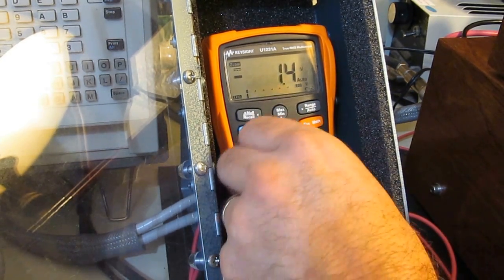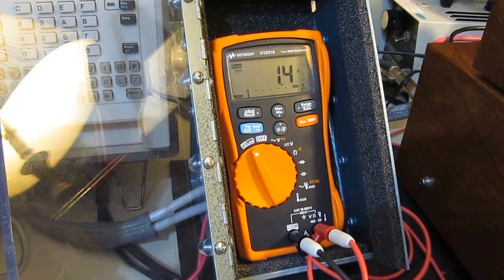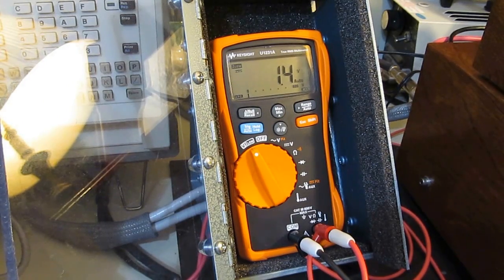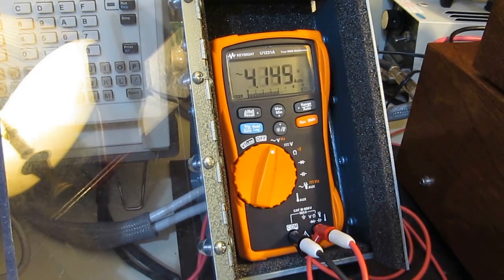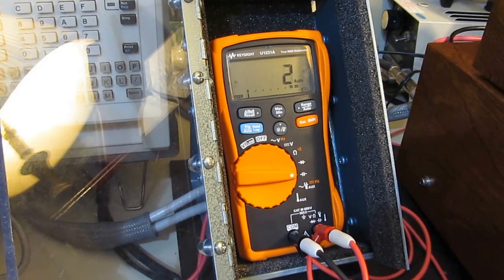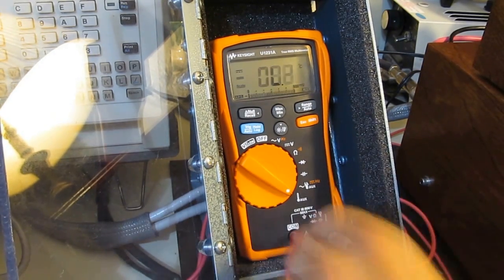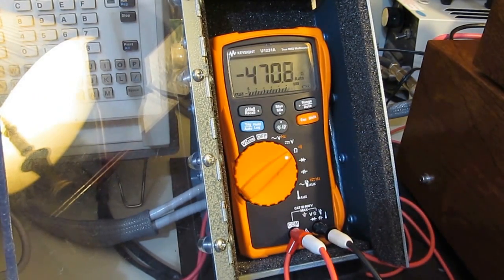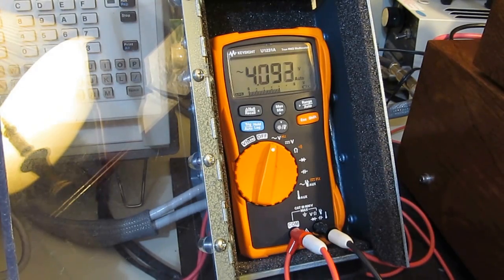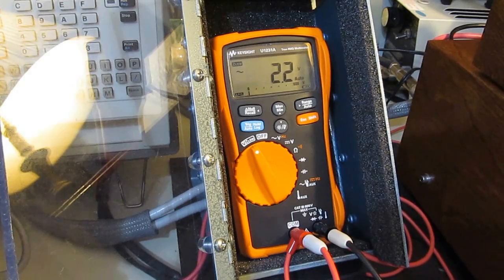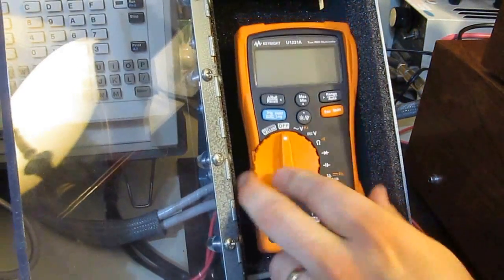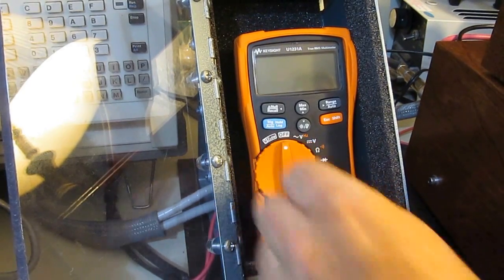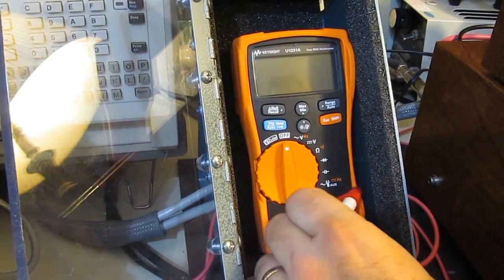I'll go ahead and functional test it. Okay, the meter survived the 1,000 volt test, no problems. This will be a 1.5 kV pulse. Okay, we'll go ahead and functional test it. The meter survived just fine.